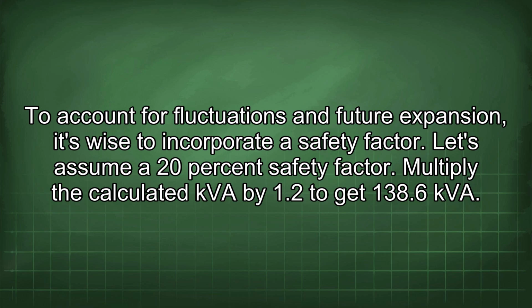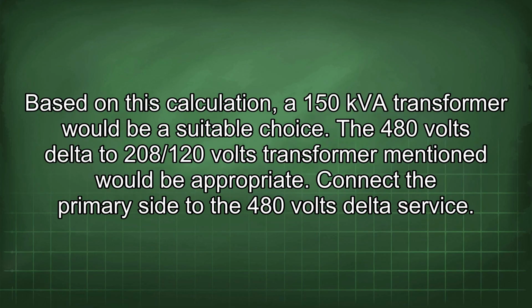Let's assume a 20% safety factor. Multiply the calculated kVA by 1.2 to get 138.6 kVA. Based on this calculation, a 150 kVA transformer would be a suitable choice. The 480 volts delta to 208/120 volts transformer mentioned would be appropriate.